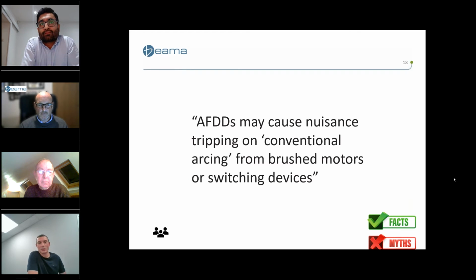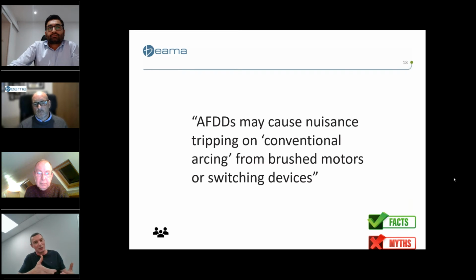Can I add to that? It's true to say in the 62606 standard, there are tests that are specifically there for immunity against tripping by appliances that do produce sparking during normal operation. So, for example, your portable drill, or switching a light switch on and off, but also masking tests, where if you introduce an arcing fault in, say, the fixed wiring and you have these appliances running at the same time, so you might have your vacuum cleaner on or your portable drill, the AFDD is designed to be able to see the arc fault that's happening and not be obscured or masked by the fact that the portable drill or the vacuum is running at the same time. So these tests form an important part of the standards.